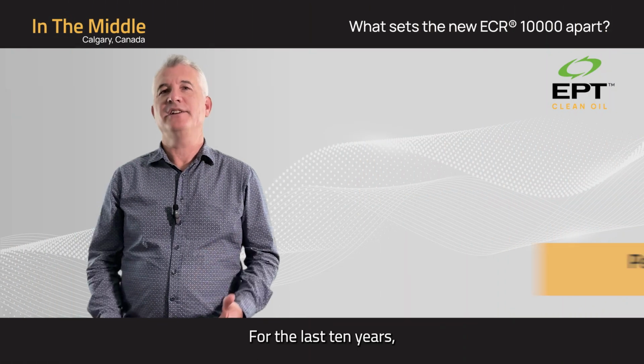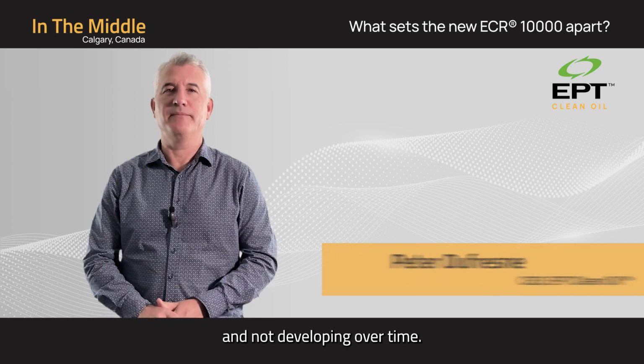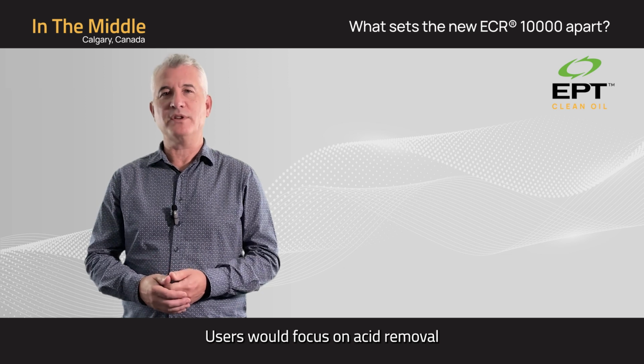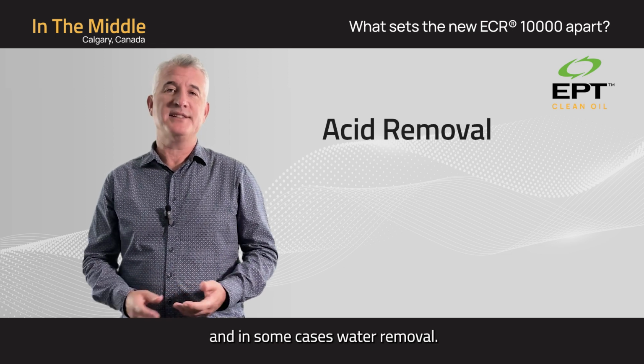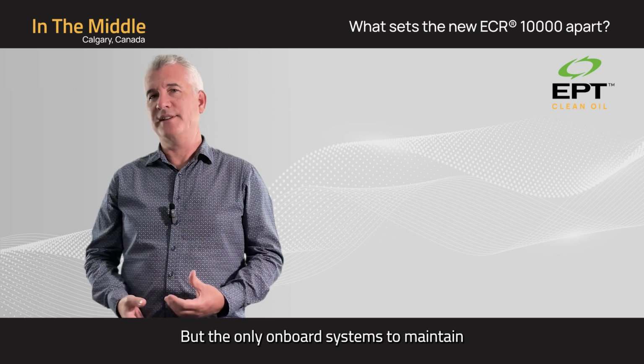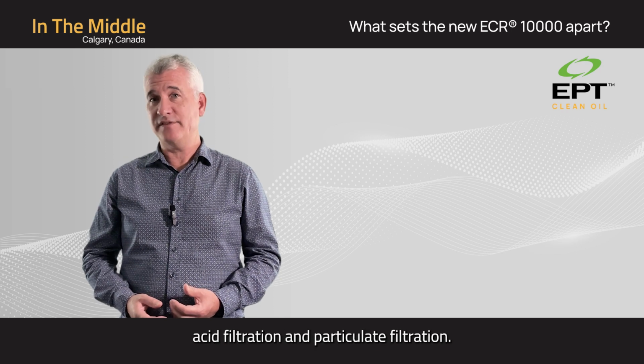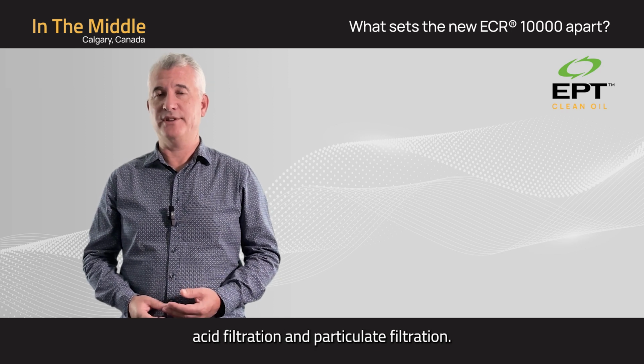For the last 10 years, EHC fluid maintenance has been relatively static and not developing over time. Users would focus on acid removal and in some cases water removal, but the only onboard systems to maintain EHC fluids have been limited to acid filtration and particulate filtration.